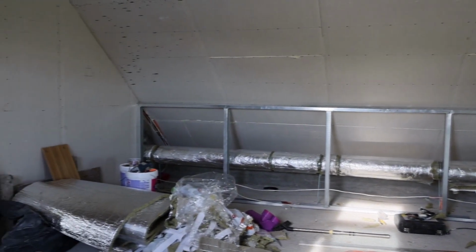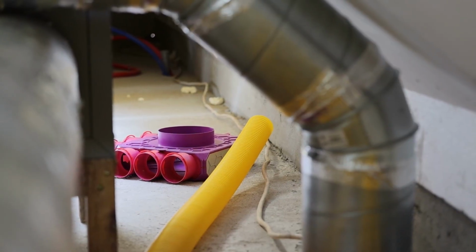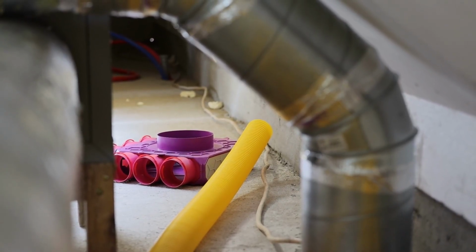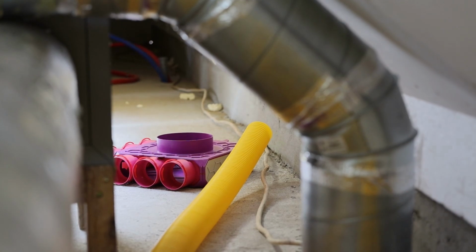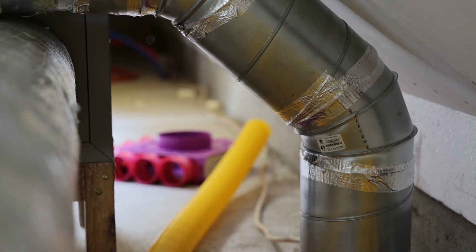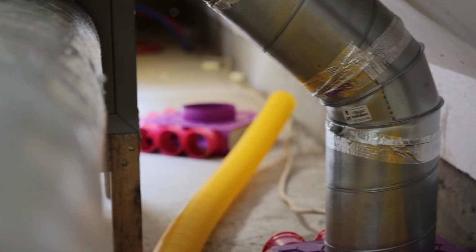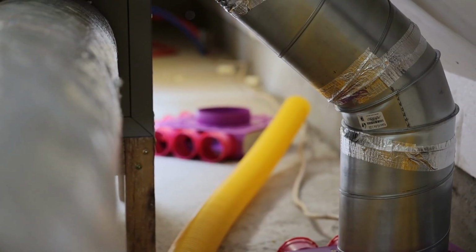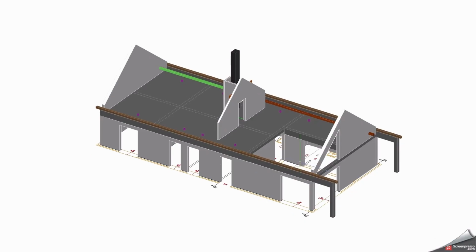I connected the 3 meter sections with sheet metal screws through the systemic nipples. It is important to remember to seal each and every pipe connection with tape, because all potential leaks will accumulate and ultimately lead to a decrease in the system's overall efficiency.